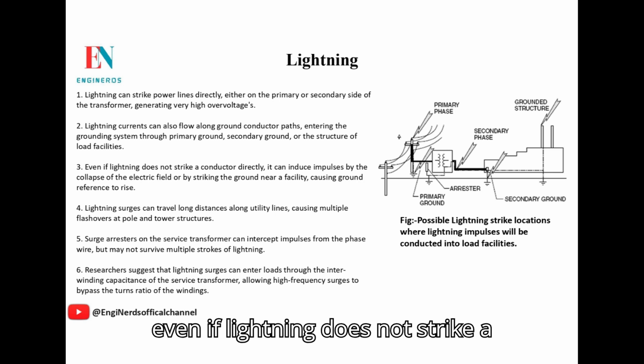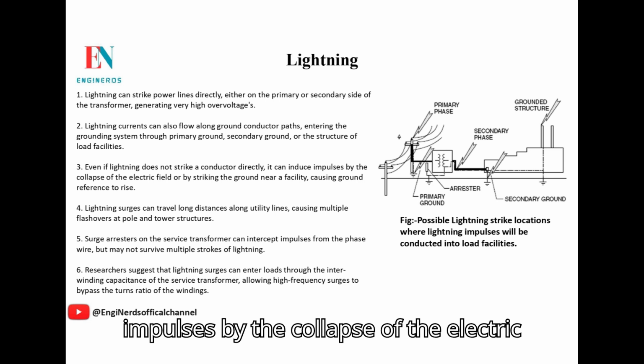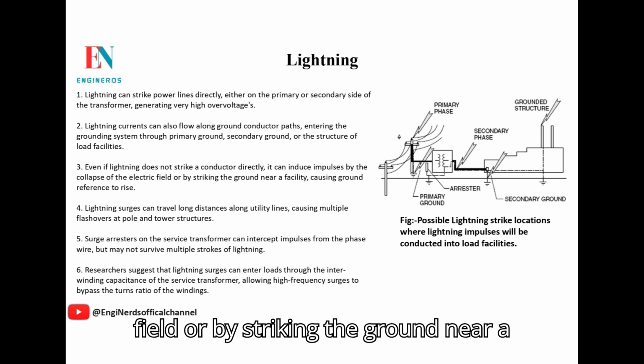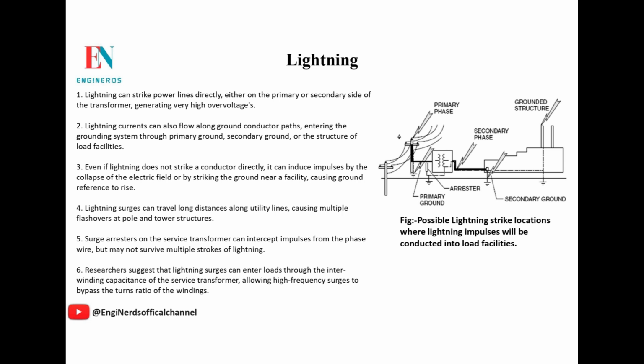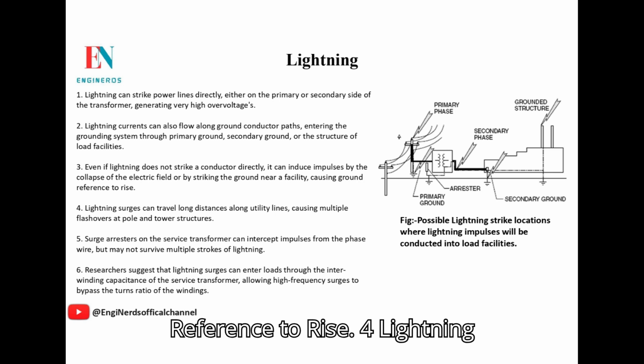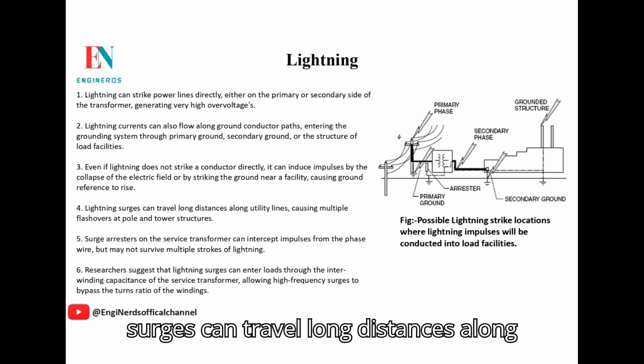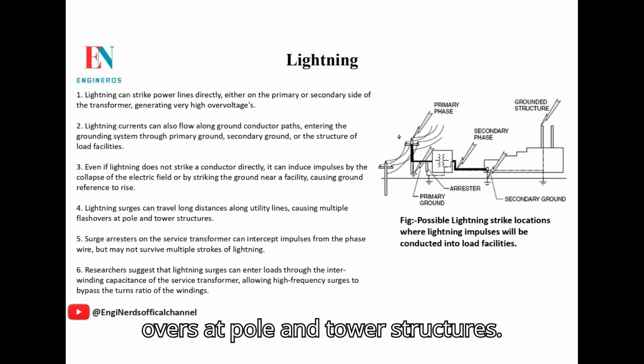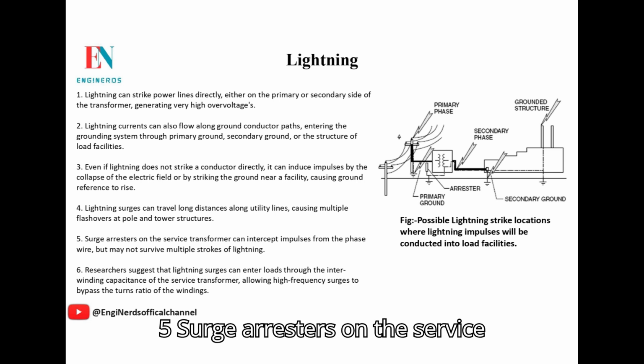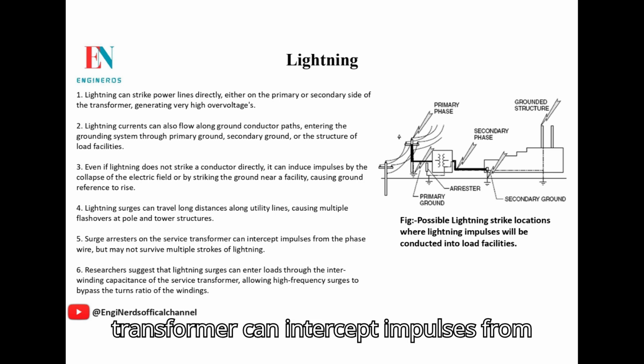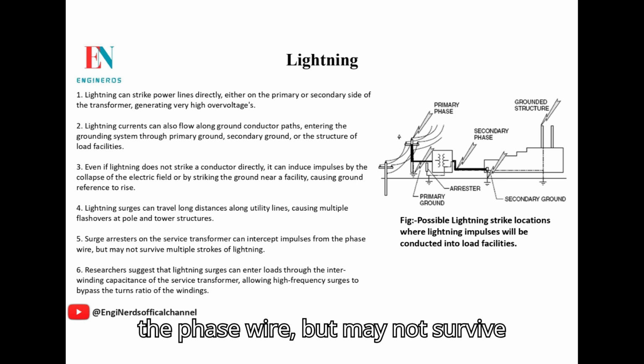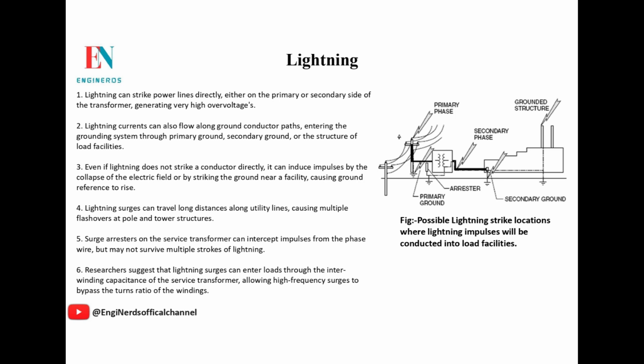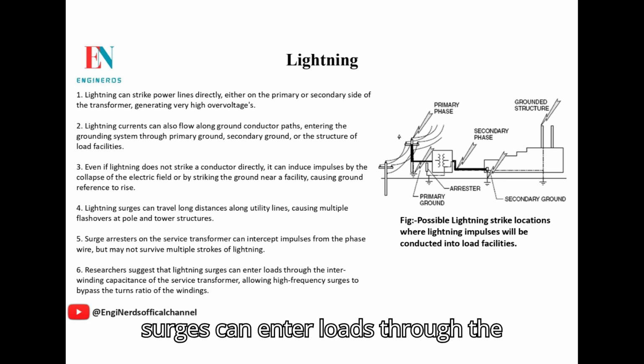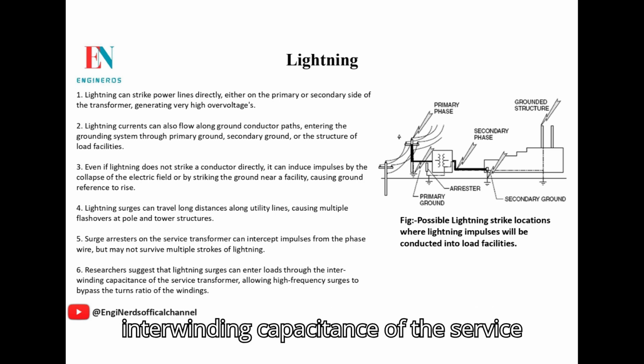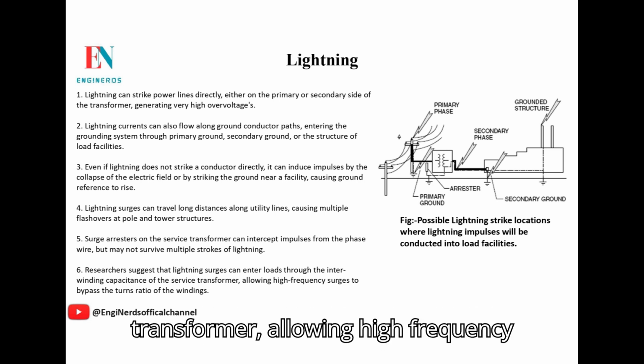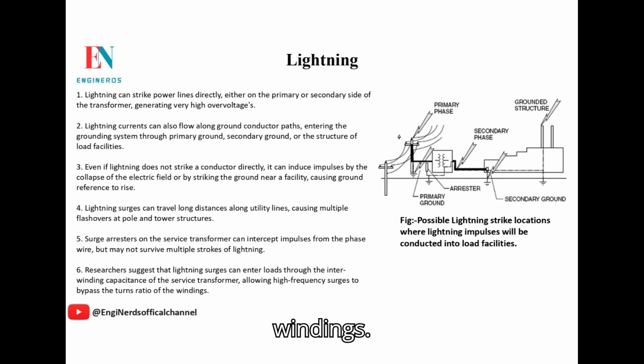Even if lightning does not strike a conductor directly, it can induce impulses by the collapse of the electric field or by striking the ground near a facility, causing ground reference to rise. 4. Lightning surges can travel long distances along utility lines, causing multiple flashovers at pole and tower structures. 5. Surge arresters on the service transformer can intercept impulses from the phase wire, but may not survive multiple strokes of lightning. 6. Researchers suggest that lightning surges can enter loads through the interwinding capacitance of the service transformer, allowing high-frequency surges to bypass the turns ratio of the windings.